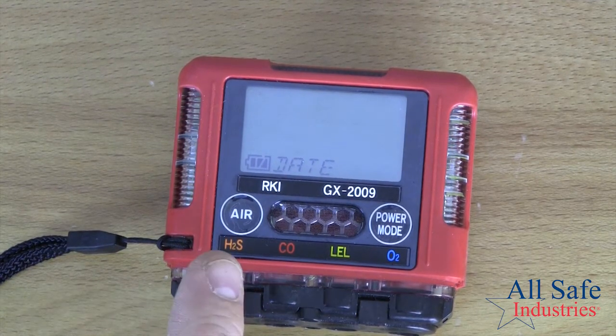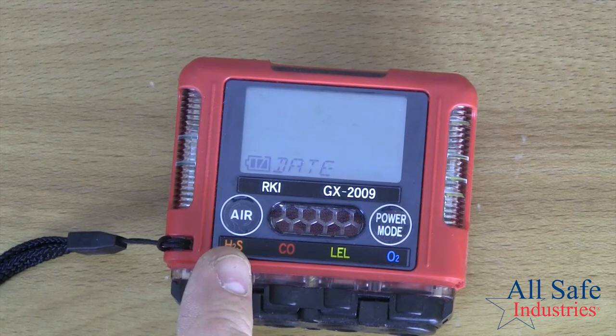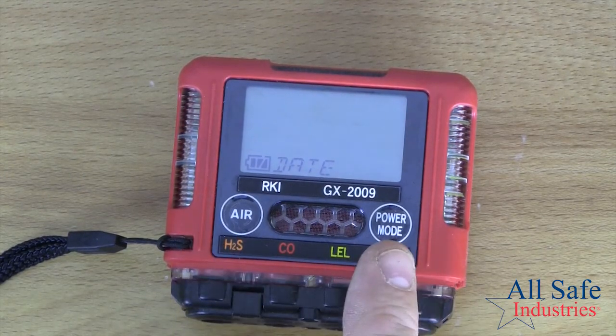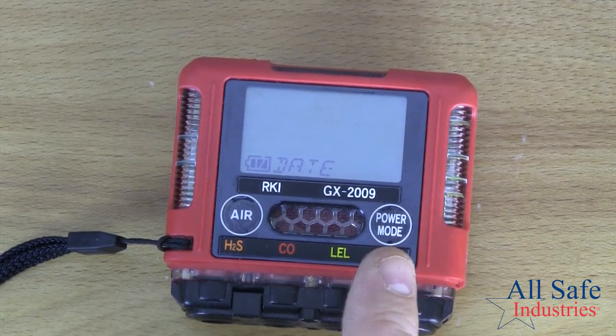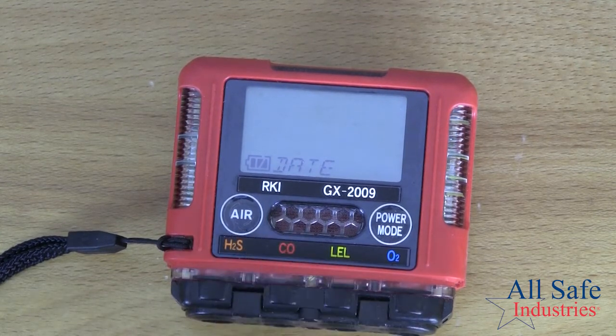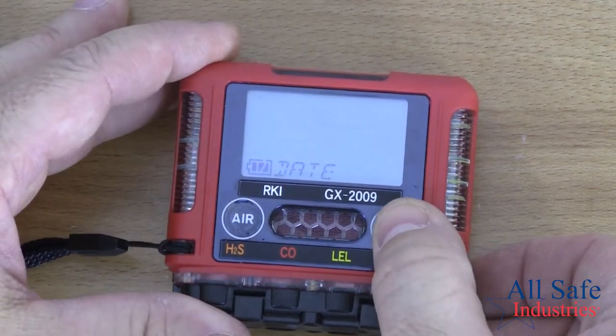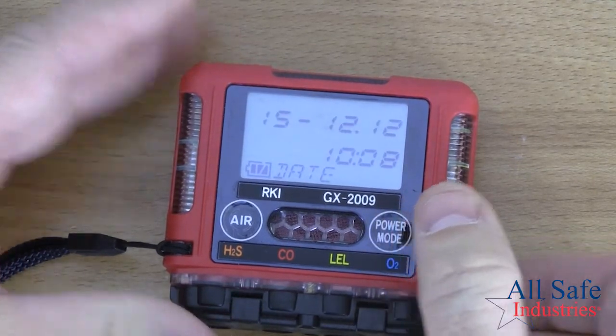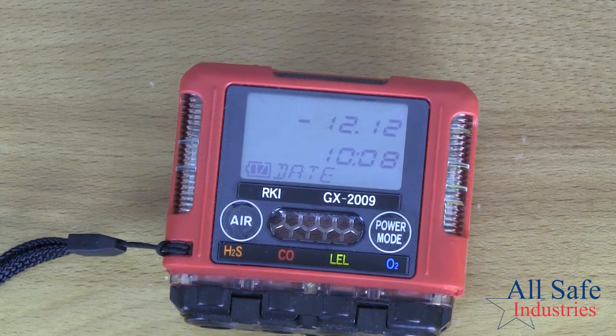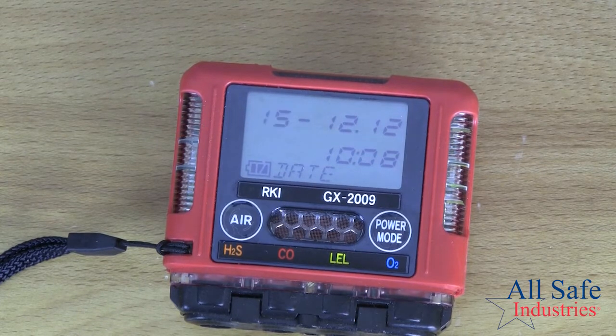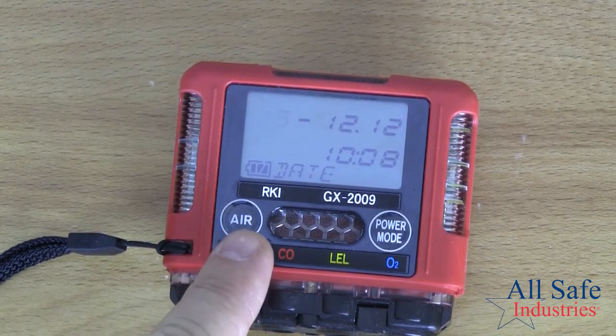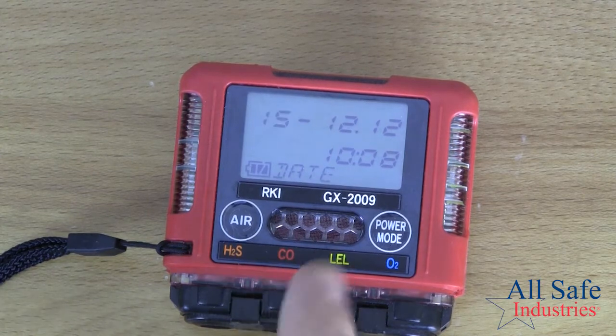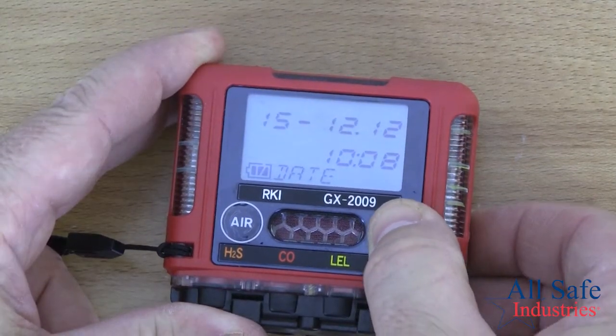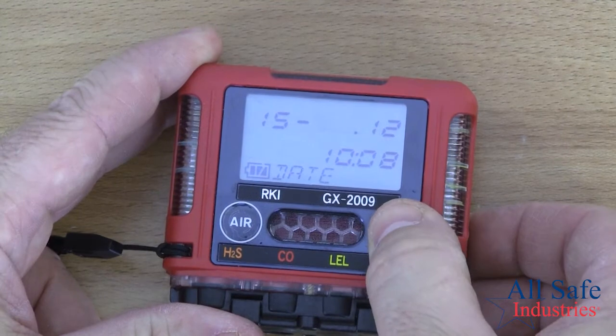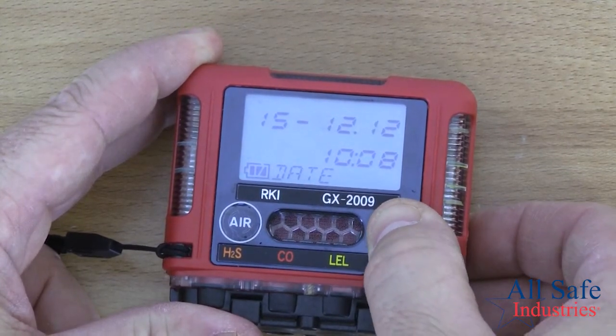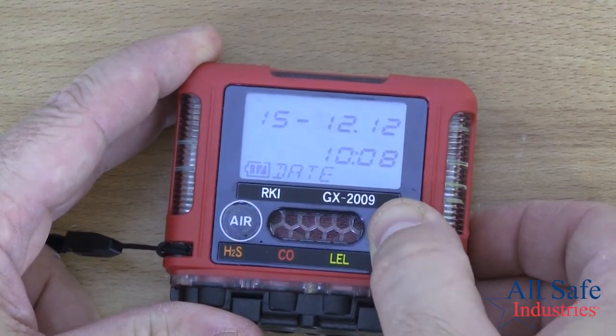And remember, earlier I was saying that the air button is like my scroll button, and my power mode button is like my select button. So if I wanted to change the date, I would press the select button or the power mode button. And now you can see the characters of the date flashing at me. And if I want to adjust those numbers, I would press the air button. If I don't want to adjust them and I want to go to the next thing, I will press the select button. And that will tab me through the different pieces of information that I can change on this screen.